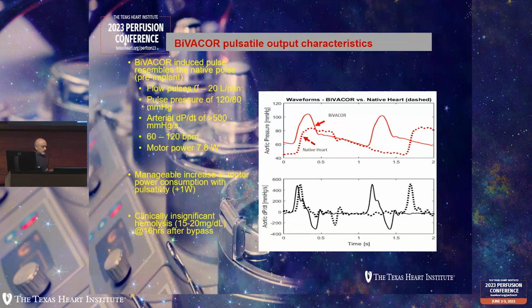Pulsatile flow, as you can see, flow pulses from 0 to 20 liters per minute, and it gave you a pulse of 120 over 80. Arterial delta P over delta T is more than 500, meaning it can provide momentarily very high flow at higher pressure if required. You can do 60 to 120 beats per minute.